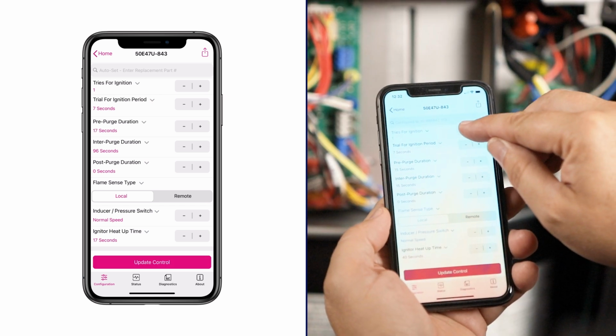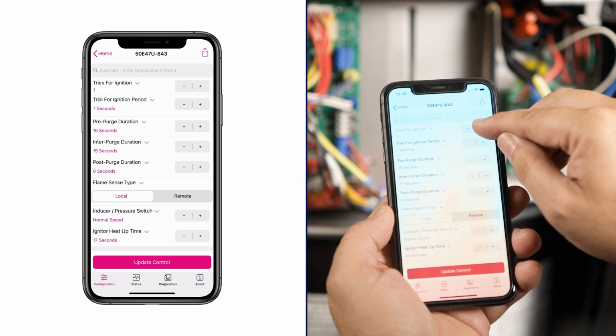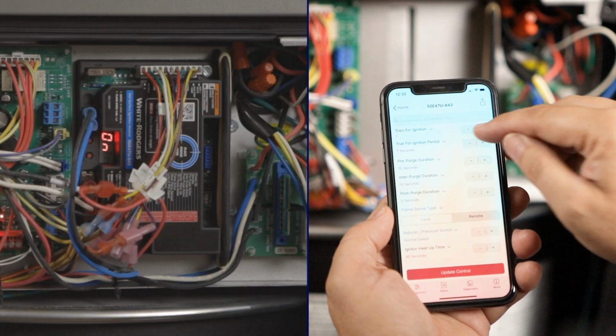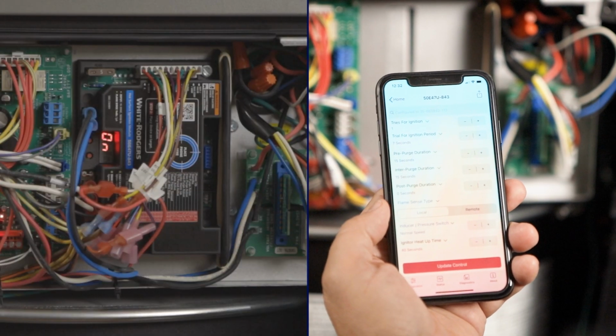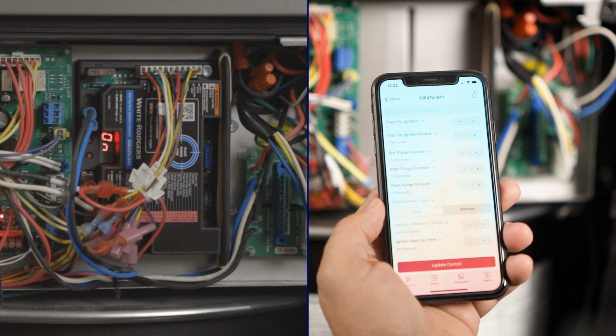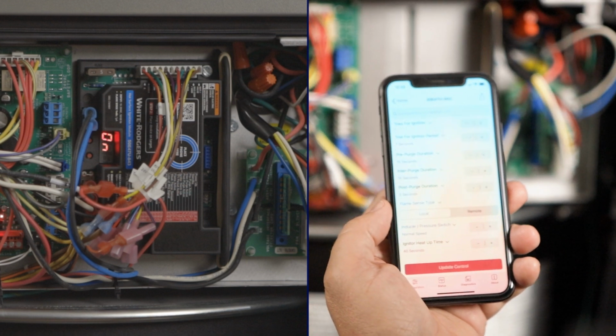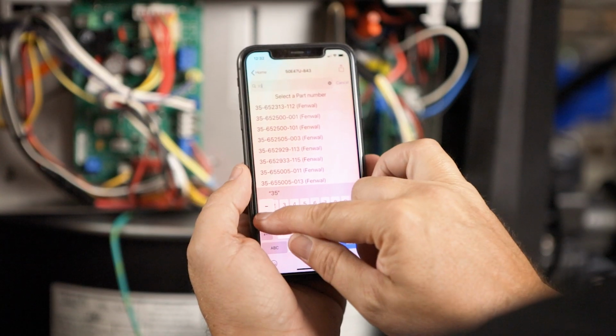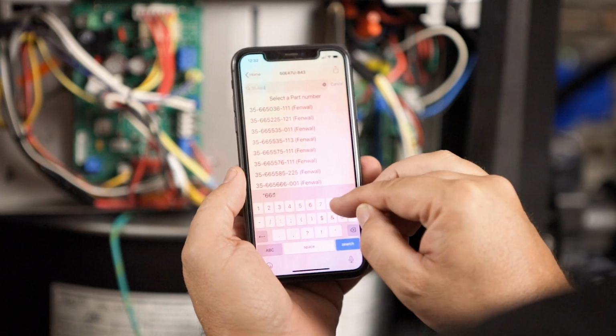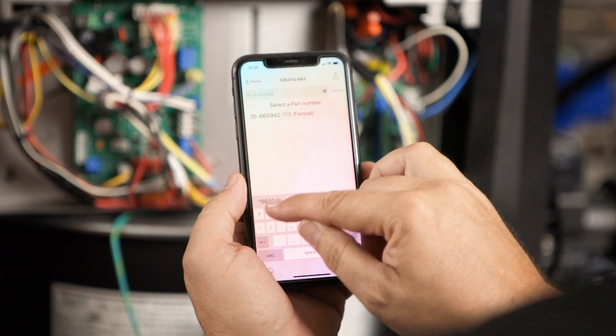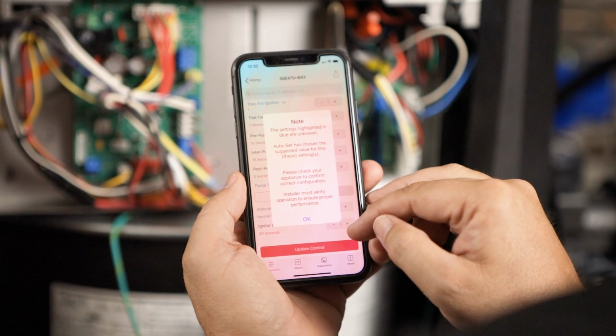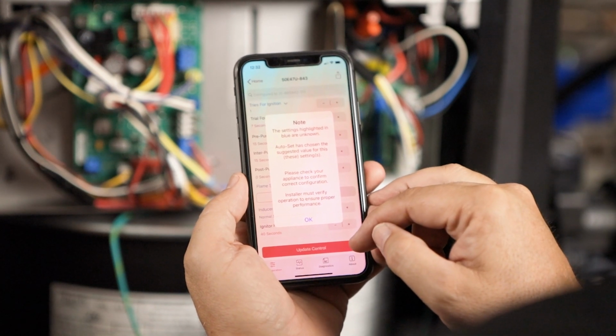If Auto Set is not used, settings can be adjusted to match the existing module. If onboard module configuration is chosen, configuration cannot be completed until the module is installed and powered up. For this application, the White-Rodgers Connect app Auto Set feature will be utilized. Type in the existing control's part number and the app will automatically display the original control's default settings.